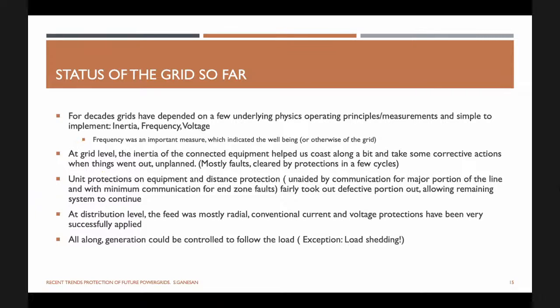Now, at the distribution level, I would say that the feed was mostly radial. Right? We have a power transformer, possibly let's say a 132 kV/33 kV power transformer, 20 MVA or 30 MVA, and that was feeding the system. And the system was radial. There's no major issue with isolating the fault with respect to a very simple overload protection aided with some of the instantaneous protection and differential protections.